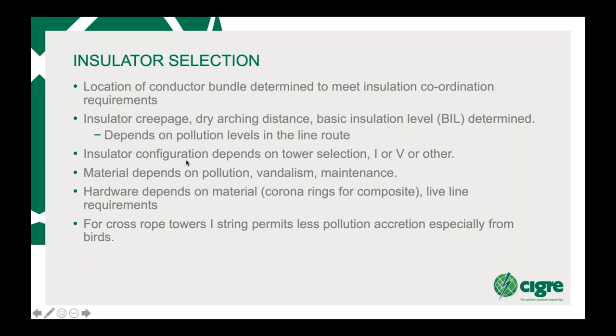Now, your insulator configuration depends on your tower selection, and you might wish to use a V string or an I string, or you might want to use an inverted Y or a Y string if you want a large amount of insulation but a very short overall insulator string length, which is normally used to increase height above ground. The material of the insulator depends on pollution, vandalism, and then maintenance. In polluted areas, we normally use composites. Most of them these days are silicone composites. Hardware depends on material, so corona rings for composite. Live line requirements are very important for compact lines, whether you need special hardware or special tools for the phase configurations that you have chosen.